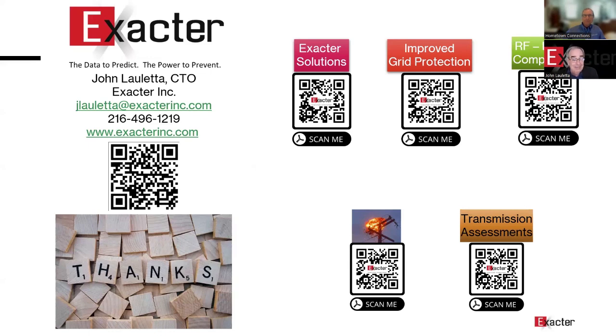Well, it sounds like it does, but there's really very little to do. If you remember that utility where we did 1,500 miles or so of work, they would have to repair on those circuits the equipment that we found. Typically in an urban setting, we find one problem every 4 miles. That's one insulator, as an example, not one pole, one insulator, or one issue that requires attention. In a suburban area, it's usually more like one problem every 7 to 8 miles, and in a rural area, it's more like one problem every 10 to 12 miles. So that's the work that the utility has to do that they wouldn't have had to do before.